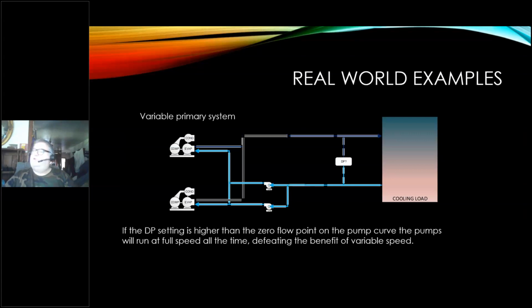Now, if I didn't have the pump curve, I wouldn't know that, because they had set this thing above the zero flow point on that curve. The pump would never reach that because basically you're asking the pump to run at a dead head condition. Even if I shut the valve off, I would never see that pressure differential at the pump. So they'd set it up so high because more is better, right? What they had thought was if I keep increasing the pressure setting, it speeds the pump up and I get more water, right? Well, that's what happened. The pump sped up, but it wasn't the right approach. It defeated the benefit of variable speed. The chillers would just sit there trying to deal with this higher flow, and it just wasn't very efficient.